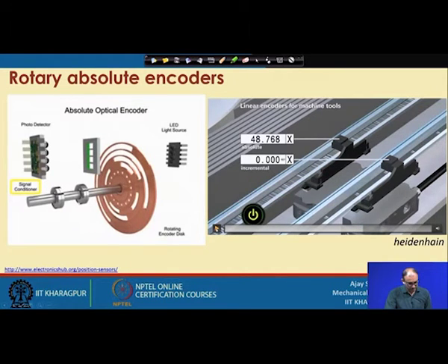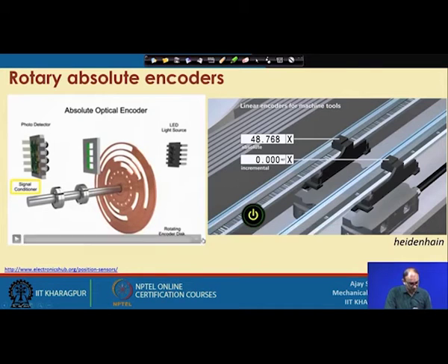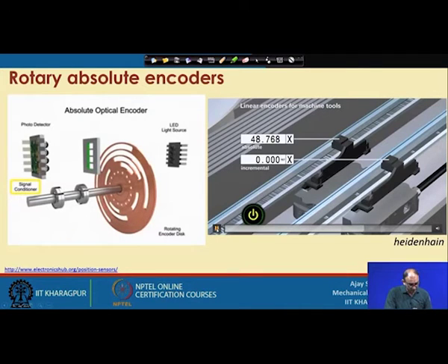Now, power is off. After switching off the power, power has come back, but you can see this absolute encoder is still showing the same result, while the other has not reached that location because it is finding the reference. If you continue with this operation, it will take some time. Now, see, it is blinking, the reference is blinking. Now it has reached.